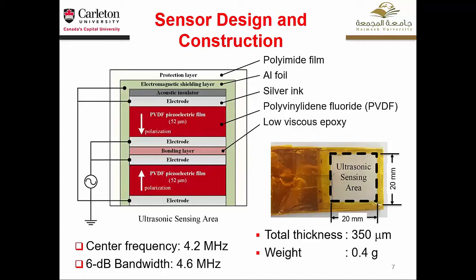So the sensor here, in this case, the center frequency is around 4 megahertz, and the bandwidth is 4.6 megahertz, which is kind of a typical frequency range of the medical ultrasound. The total thickness of the sensor is 350 micron, and total weight is about 0.4 grams. So it's quite lightweight and bendable and flexible.